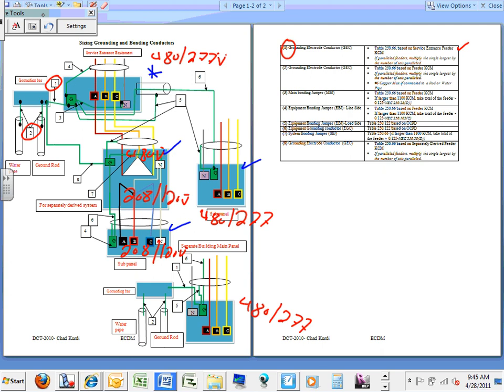Number three, Spencer, is actually the system bonding jumper. Can you guys see it's going from the neutral to the ground? You have to bond the neutral to the ground at the service. You have to bond the neutral to the ground at the service. How do you size the main bonding jumper, guys? It's 250.66, right? Based on the service entrance conductors or the feeders of the service entrance conductors. And if larger than 1100 kcmil, you take 12.5% of the feeders. We're going to take an example in a second.